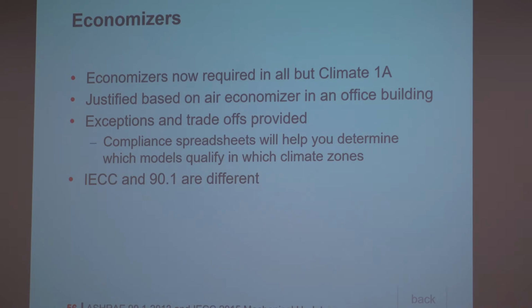So this is where areas where it's slightly different. IECC 2015, so all of Pennsylvania will have this aggregation clause in it. It's slightly different in 2018, but not that much for IECC. So the premise is, okay, I have this exception right now from having to have an economizer if my individual terminal unit, my fan plus coil, were less than 54,000 BTUs, which is about 4.5 tons. I didn't have to have economizers regardless of how many of those things I had.